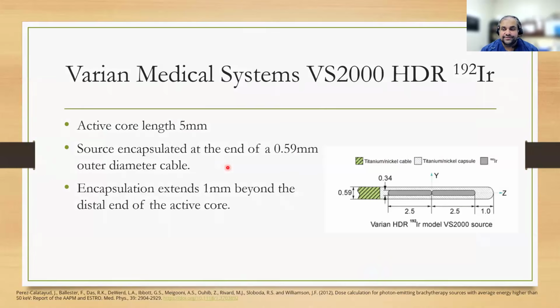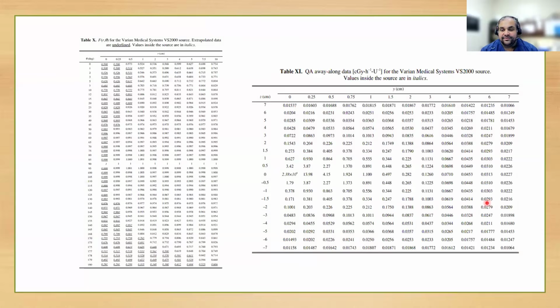Similarly, for the other source, you can see over here the source design encapsulation consists of 0.34 millimeter diameter and 2.5 millimeter long cylinders with semi-spherical ends, and the radioactive material is uniformly distributed in these two pellets. Encapsulation again extends 1 millimeter beyond the distal end of the active core. And similarly, you can see the data that's provided in AAPM report 229.